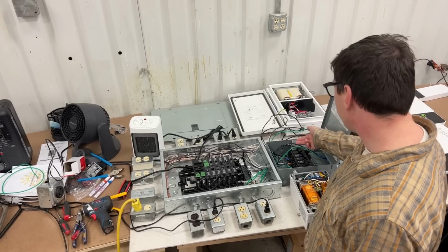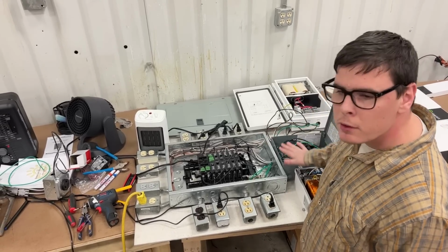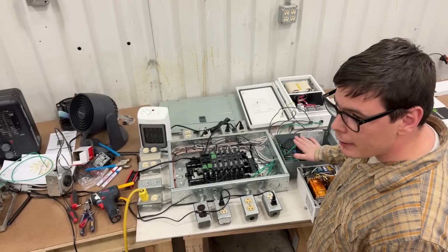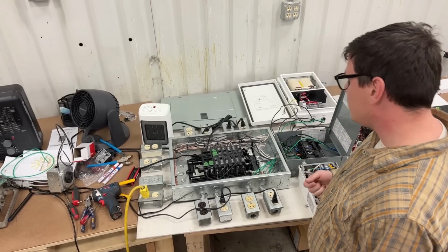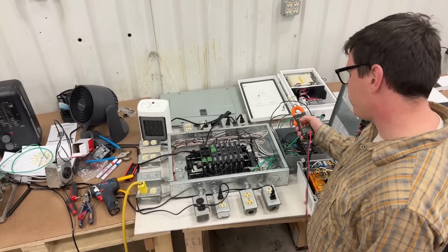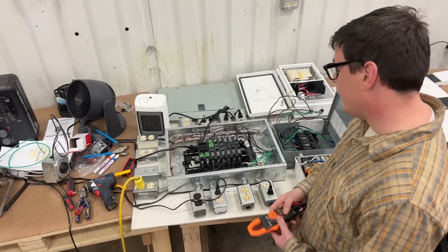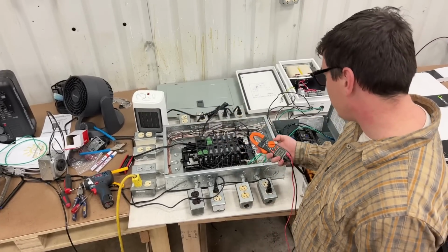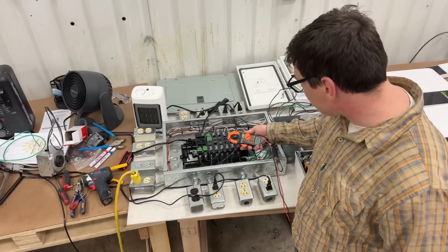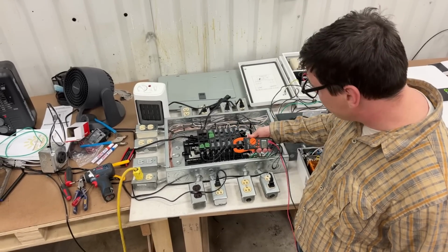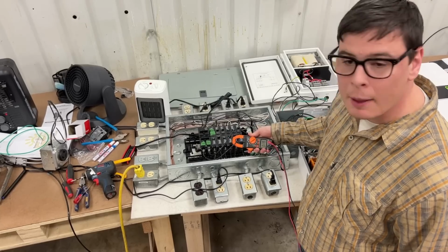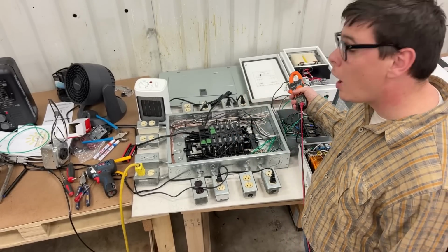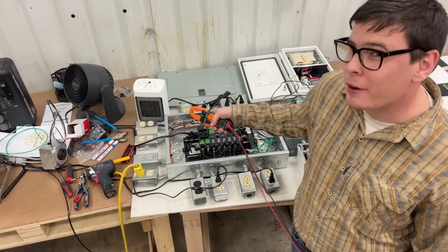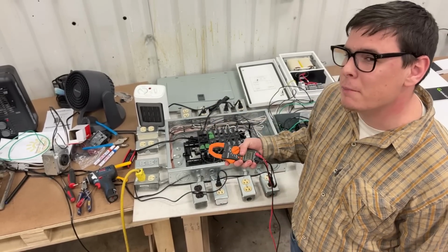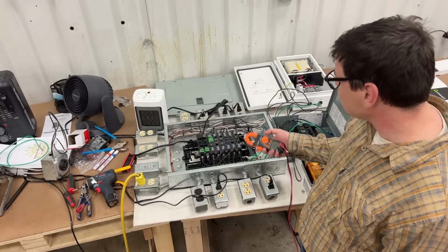Again, you can pull your 240s off of the 240 volt combiner panel, and your 120s, if you go this route. It's pretty straightforward. I've got a bunch of these heaters running right now. If I look at amperage, I'm pulling 28 amps on one leg, 11 amps on the other. So this is showing the product downstream of the transformer. So this is where you actually achieve the ability to control the situation.